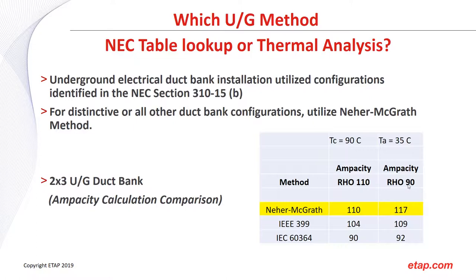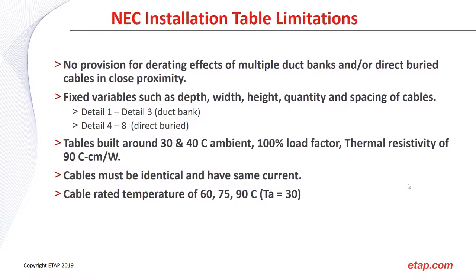This leads to the conclusion that both IEC and NEC installation tables provide some safety margin — which is a good thing. However, whenever we fall outside the table limitations, we need to perform a thermal analysis calculation. Key limitations include: no provision for derating effects of multiple duct banks and direct buried cables in close proximity, and fixed variables for depth, width, height, quantity, and spacing of cables.